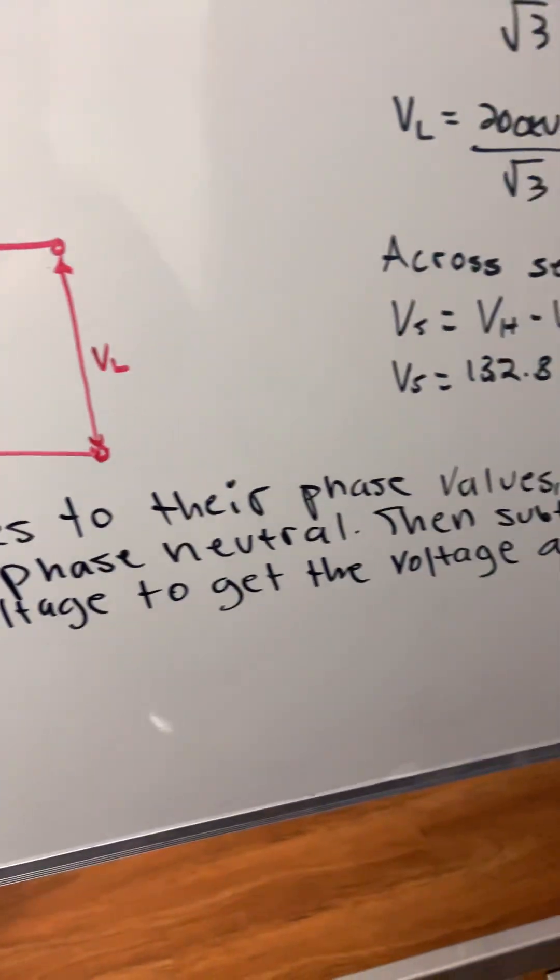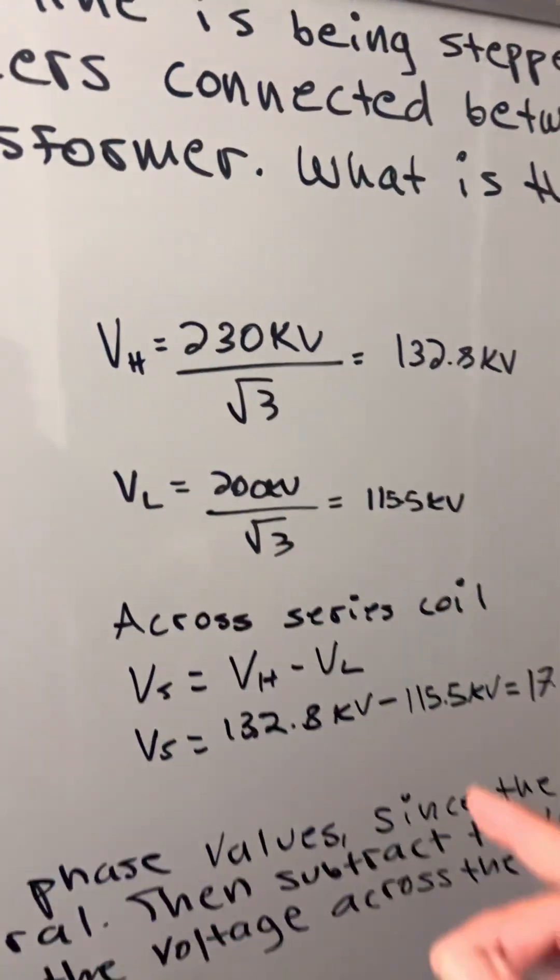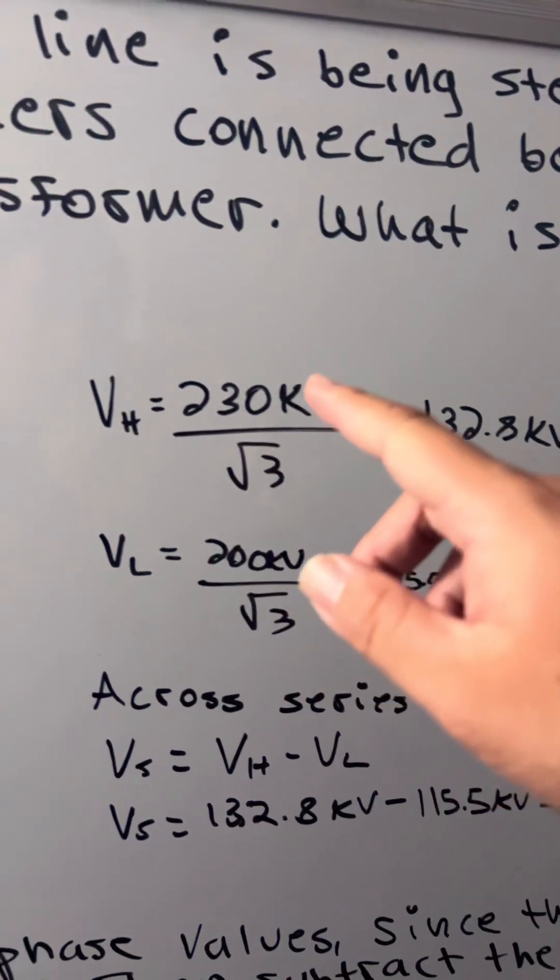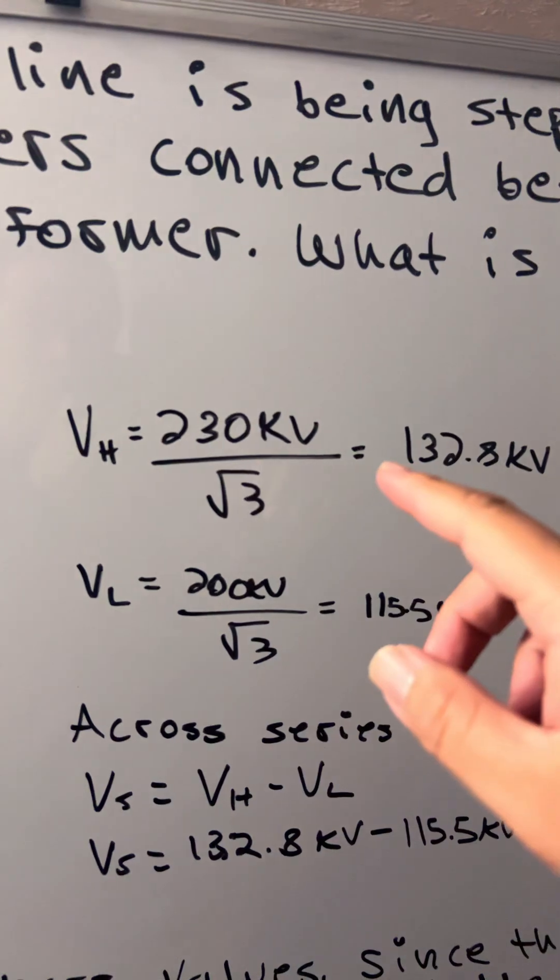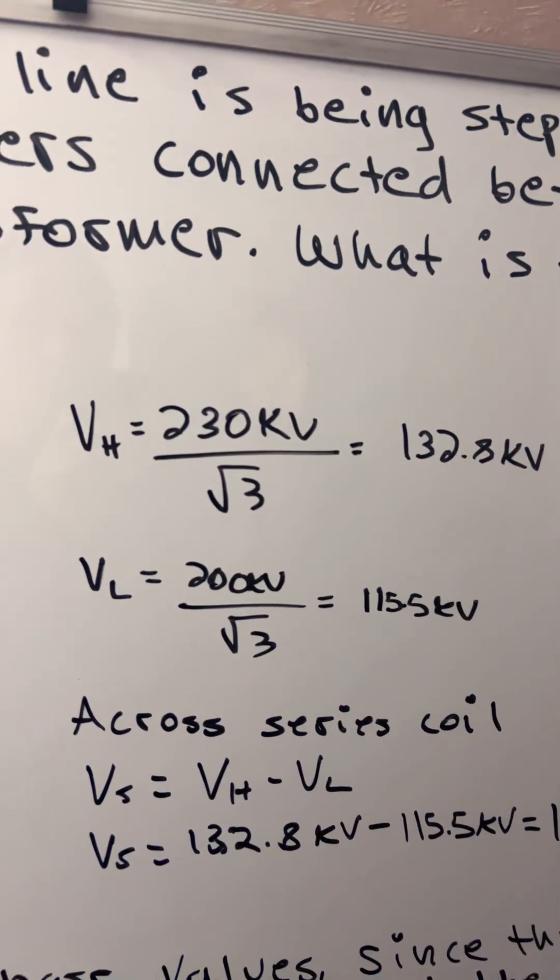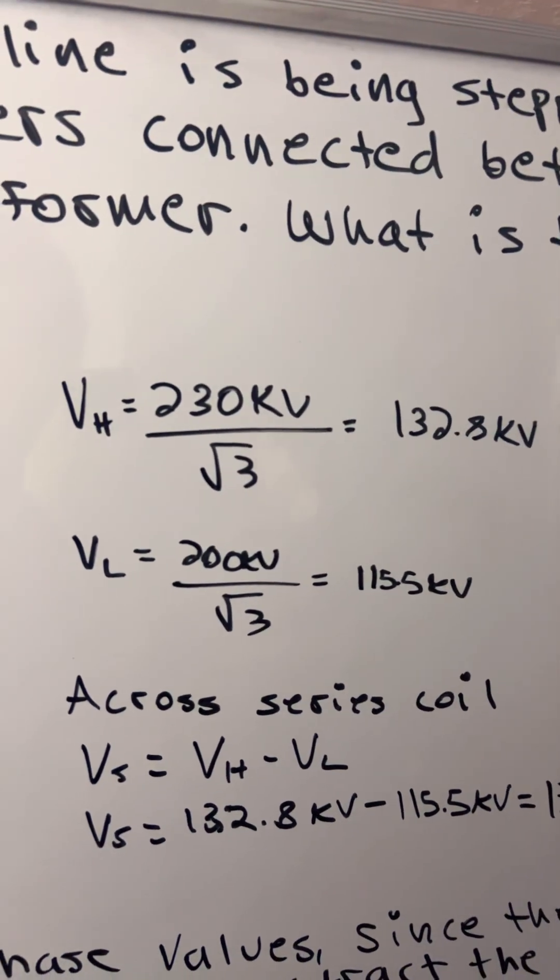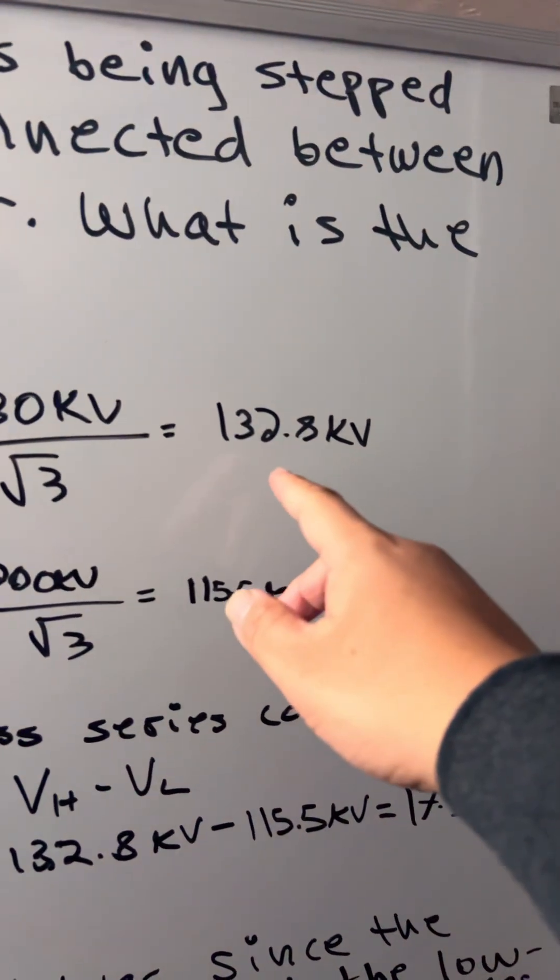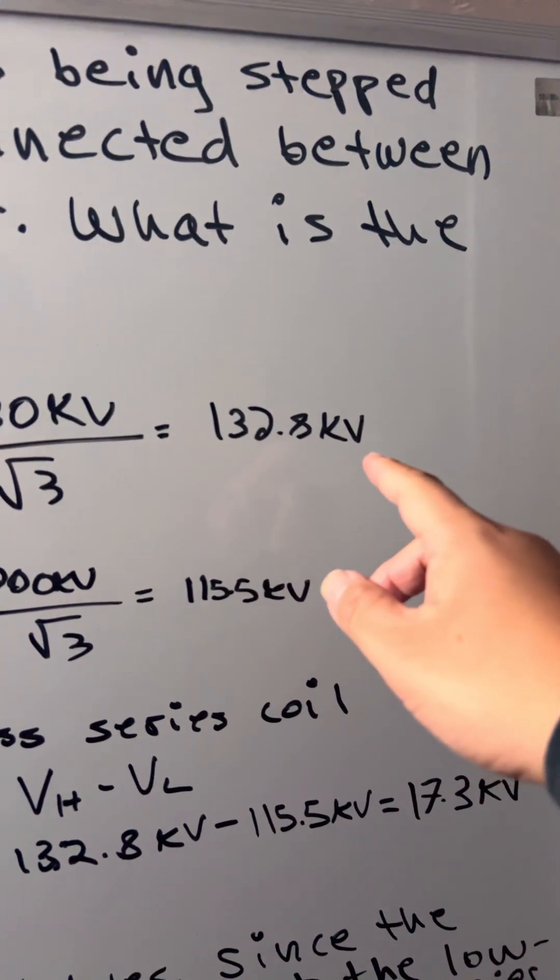To get the voltage across the series coil, this is the high voltage. So we have 230 kV, we're going to divide that by square root of 3, and that will give us 132.8 kV.